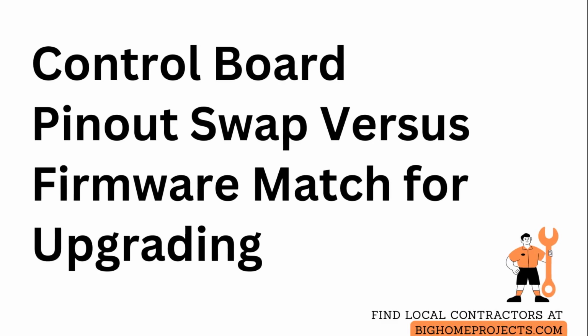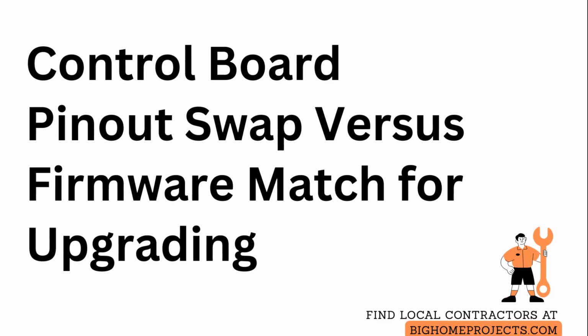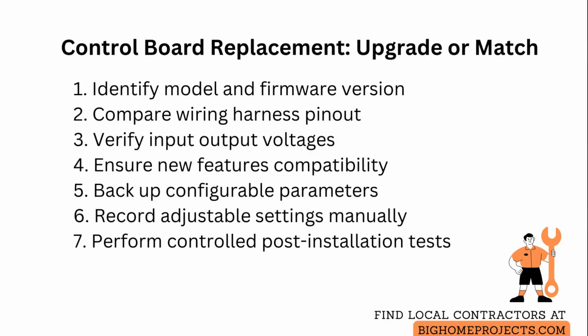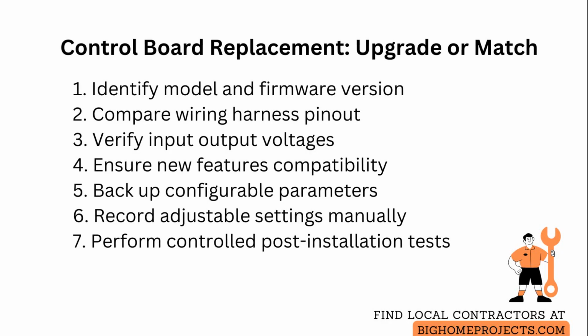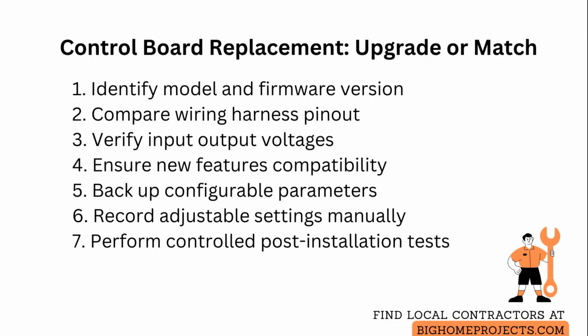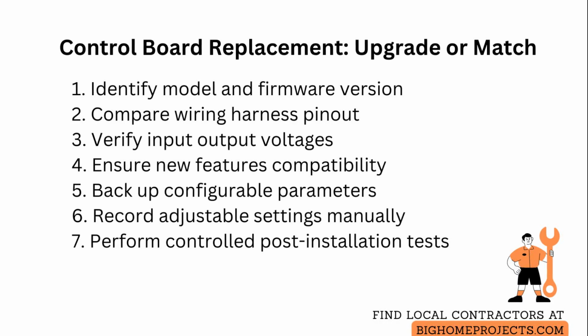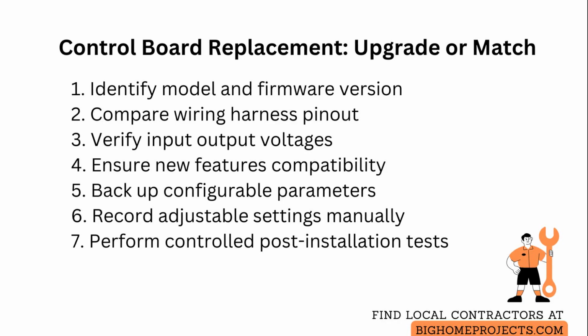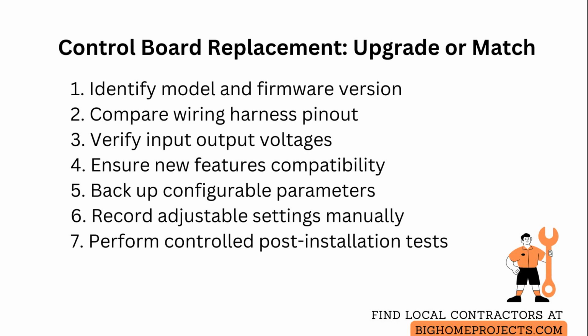Should I replace my control board with the same model, or can I upgrade to a newer one? Start by identifying the exact model and firmware version on your existing control board, because compatibility hinges on both physical connections and software. Check the wiring harness pinout against the replacement board by comparing each wire color and terminal label and trace sensor and actuator voltages with a multimeter, so you can confirm expected signals before swapping parts.